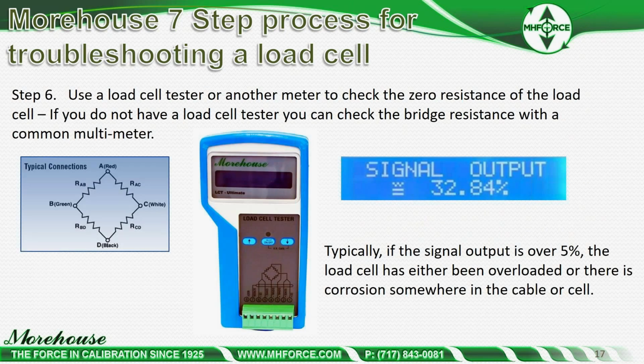Step 6, use a load cell tester or another meter to check the zero resistance of the load cell. If you do not have a load cell tester, you can check bridge resistance with a common multimeter. With a common multimeter, you can pin A and D, or if it's a Morehouse shear web, A and D for excitation, C and B for signal. You should get 350 ohms plus or minus about 3.5.